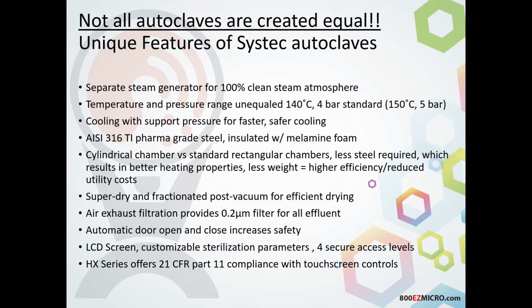We use a very high grade of stainless steel for the vessels inside of the system. It's an AISI 316 Ti, so there's a bit of titanium in there, pharma grade steel, and it's insulated with melamine foam. In addition to that insulation, quite often folks would be buying an autoclave where it says we have a vessel and a jacket, and the jacket has to be maintained all of the time. It's extremely inefficient. Then also what we're doing is keeping that jacket heated, so we're constantly running power to it, whether the instrument is being used or not.